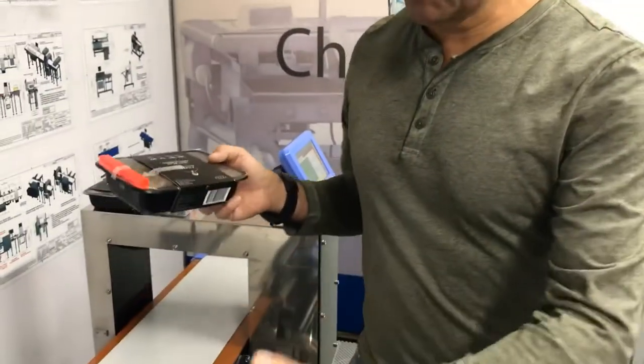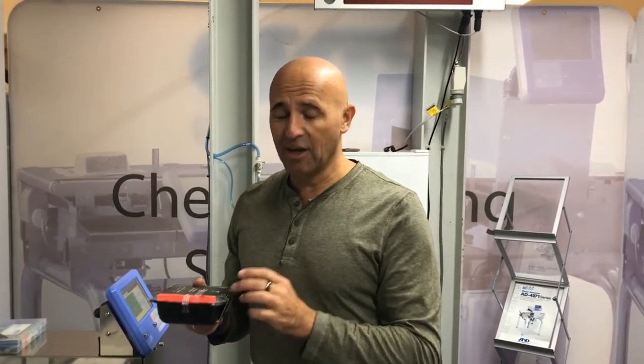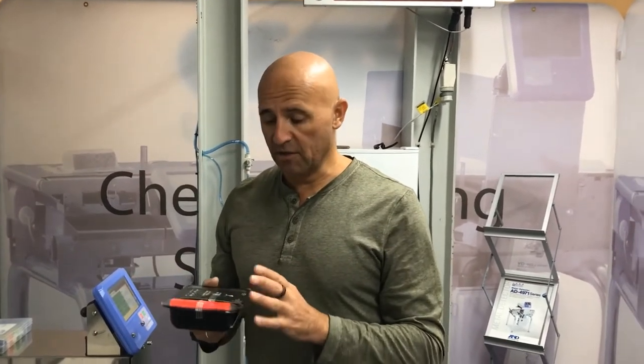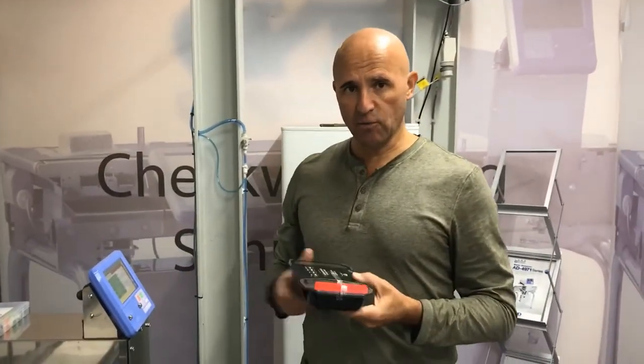When it comes to synchronizing your inputs, outputs, and your rejector, that's really important to understand. We have no control over where a contaminant is going to appear in a pack, so if your packs are on the longer side, it's probably really important to activate the photo eye synchronization feature when programming your metal detector and your checkweigher. Thanks for watching.